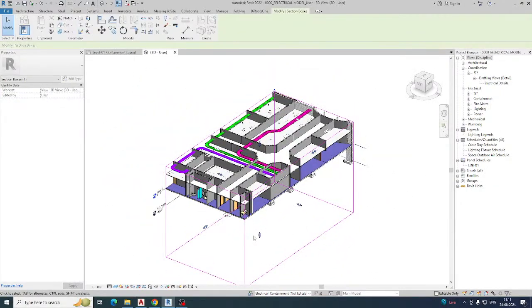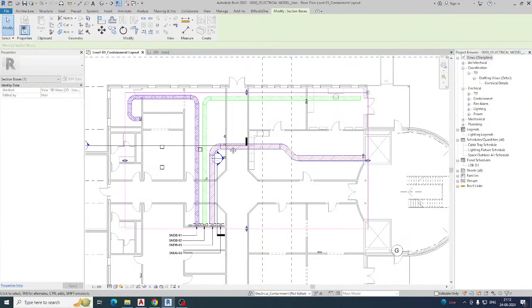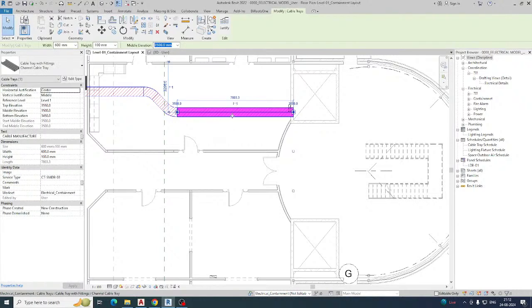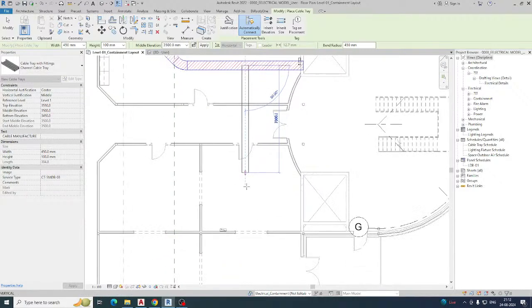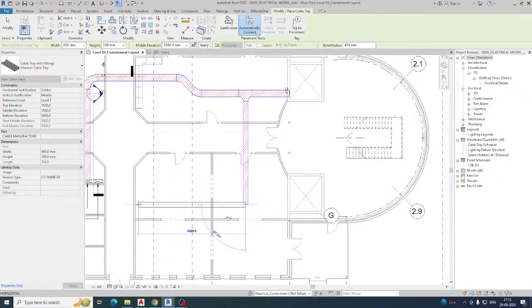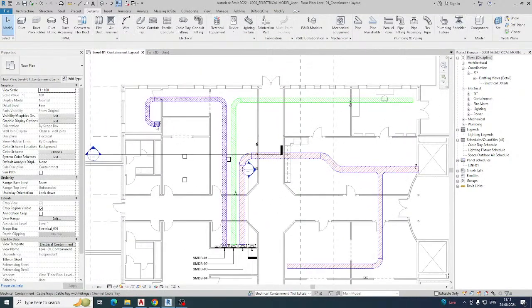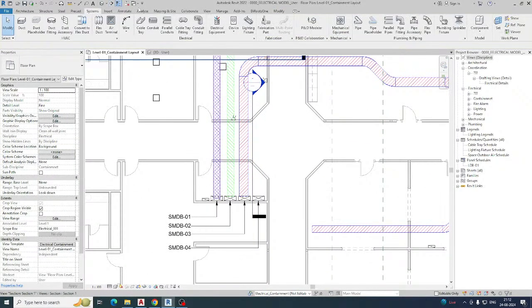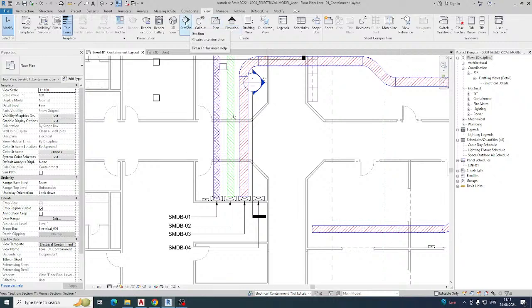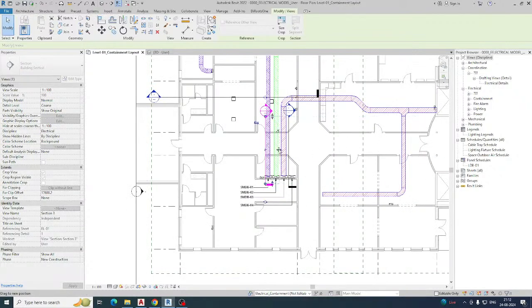Once applied, the colors reflect automatically in the 3D view. Using service types, you can distinguish all cable trays in 3D. If you need to create a branch, use Create Similar. To change the cable tray size, select it and draw. To drop a cable tray to a panel, create a section view — you can get the section tool from the View tab.